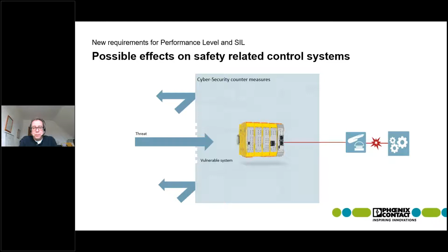The idea is to separate the automation system into different so-called zones. One zone, zone A, which you see in the center on the left side with the yellow controller, includes the safety-related sensors and actuators, and also the safety logic controller. This is the so-called core safety equipment. Zone A contains all directly related safety parts of the control system.